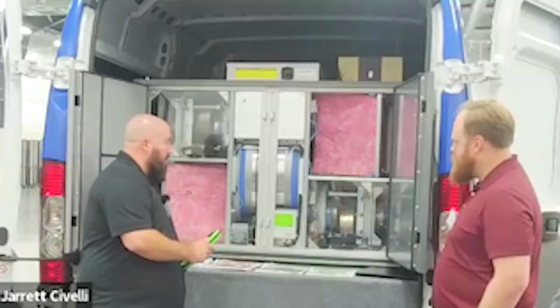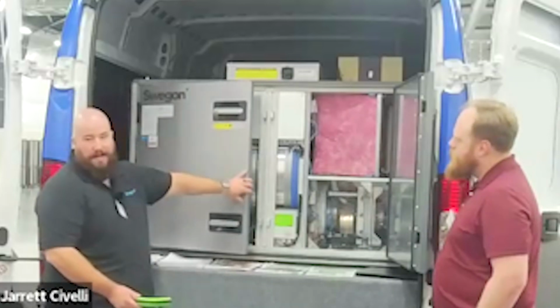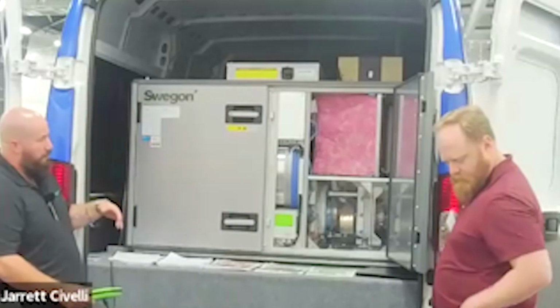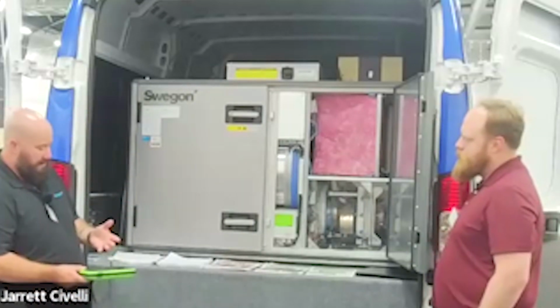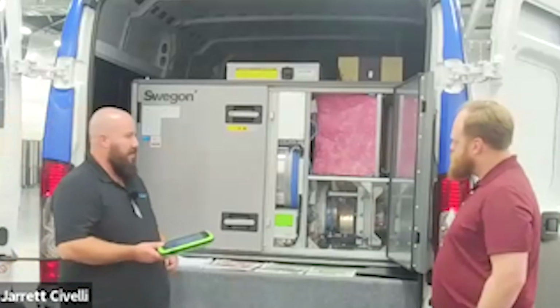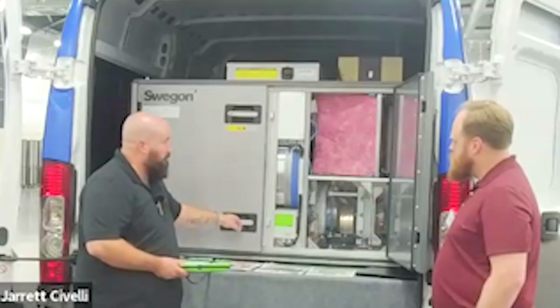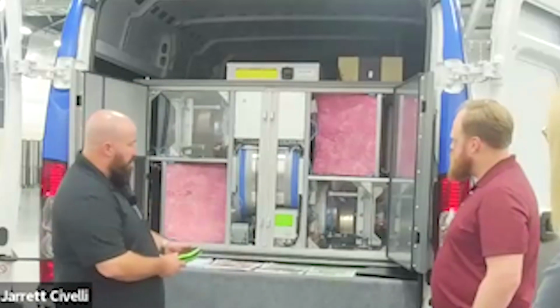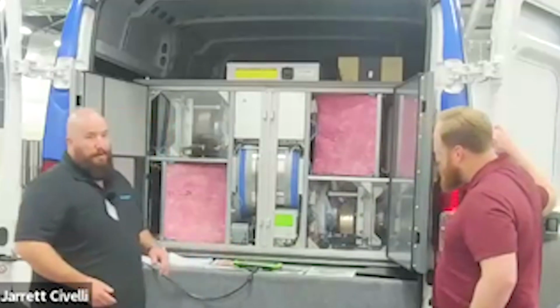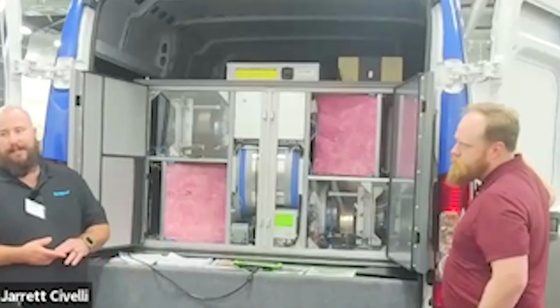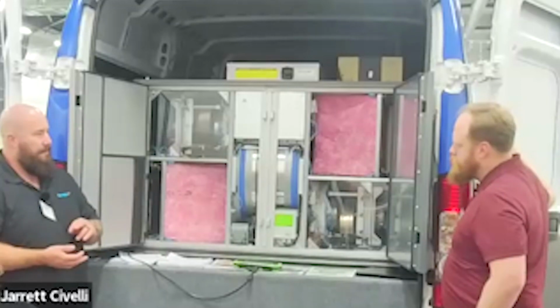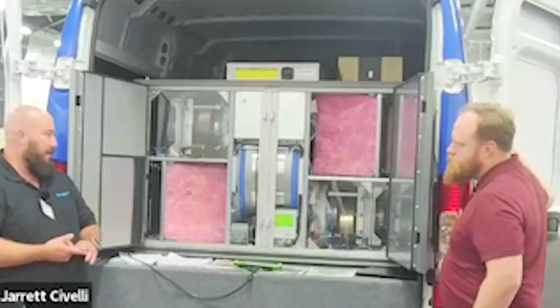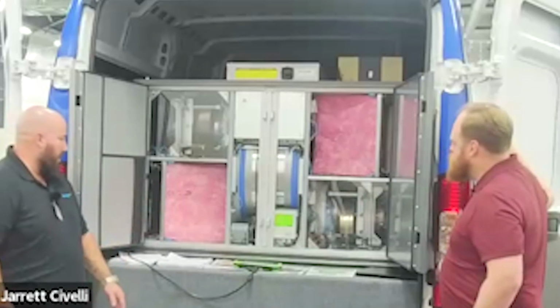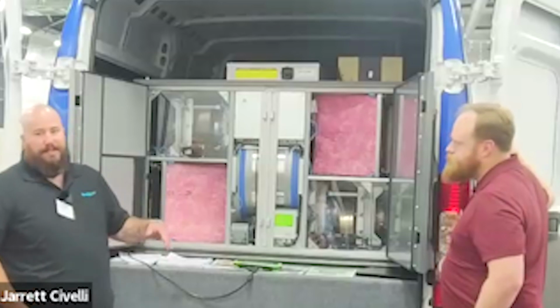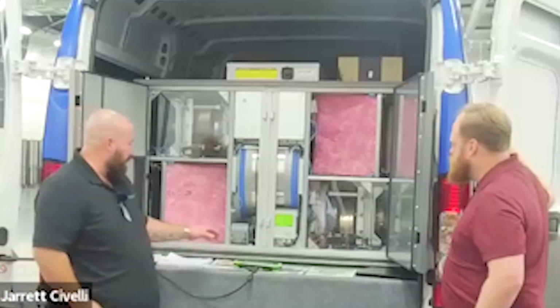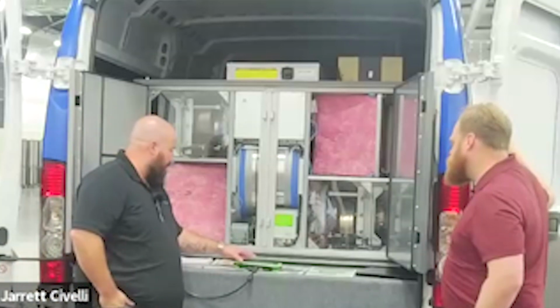This controller can either be left on site with this bracket, so you could mount it on the ductwork next to it, or a technician can take it with them—our in-house technician carries one with him just in case this one goes missing. Or you can do everything through a computer. For energy management systems, we can accommodate pretty much any system out there—Metasys, BACnet, Modbus—for larger commercial buildings, the most common being BACnet over IP. You just put an Ethernet cable in there and control it with your BMS system.